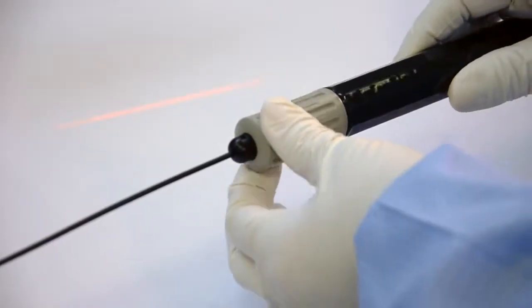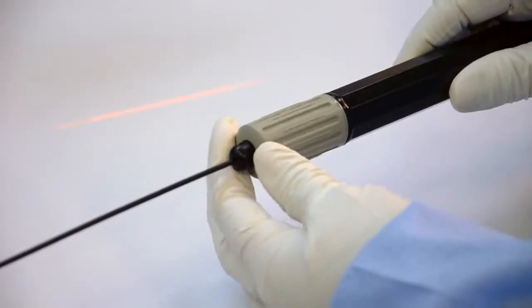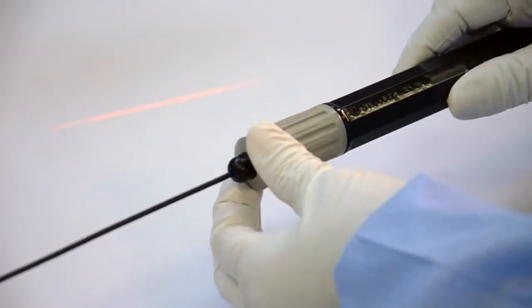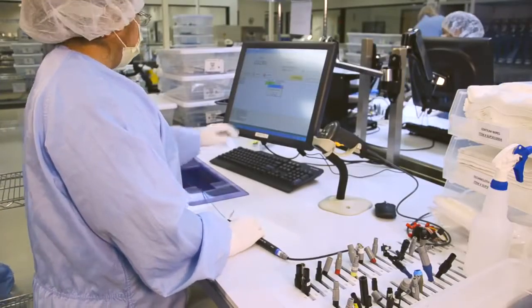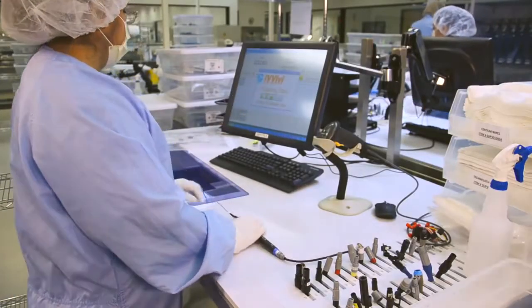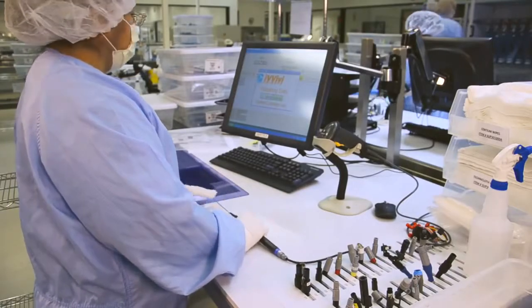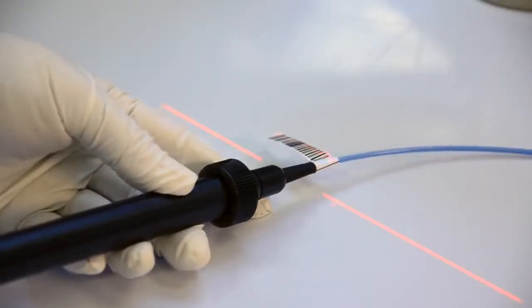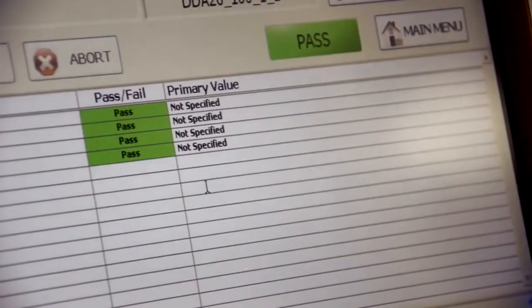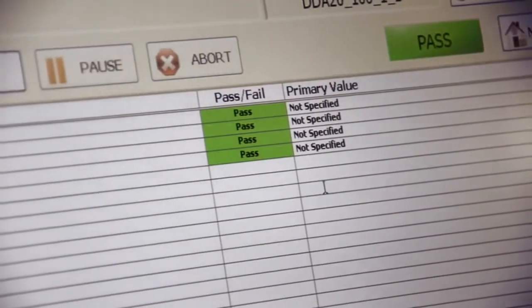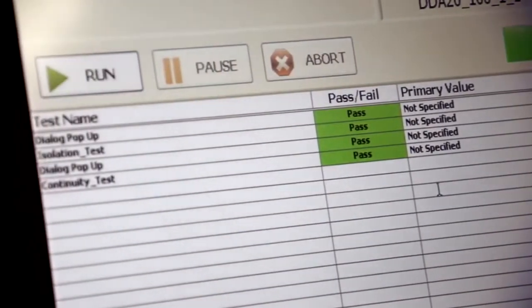Each electrode and corresponding pin of the catheter handle is verified and compared to predefined threshold resistance values. Isolation testing detects short circuits in catheters, which is typically caused by a breakdown in electrical insulation. These short circuits are detected by measuring the electrical resistance between electrodes.